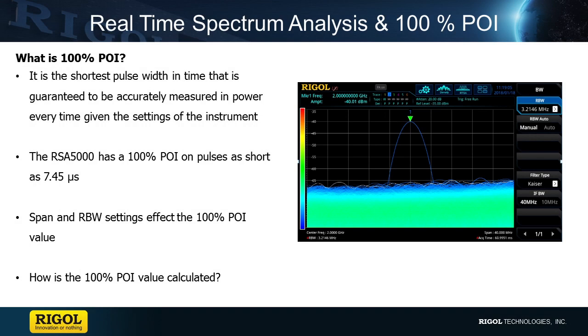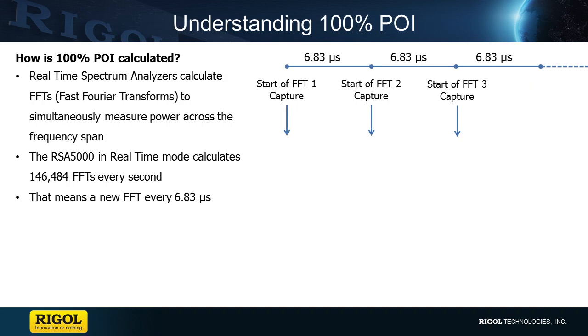Let's take a quick look at how the 100% POI, or probability of intercept, is calculated on a real-time spectrum analyzer. RIGOL's RSA5000 has a 100% POI on pulses as short as 7.45 microseconds — but how do we know that? A real-time spectrum analyzer uses FFTs, or fast Fourier transforms, to simultaneously measure power across the span. The RSA5 calculates its FFT every 6.83 microseconds.